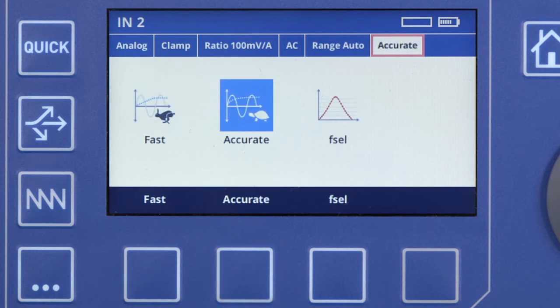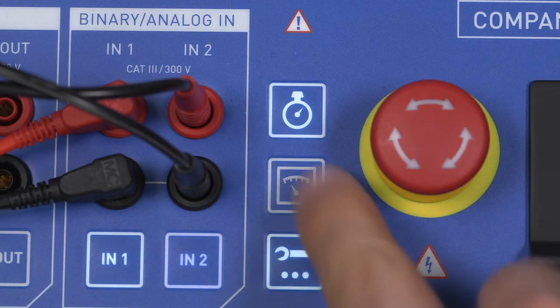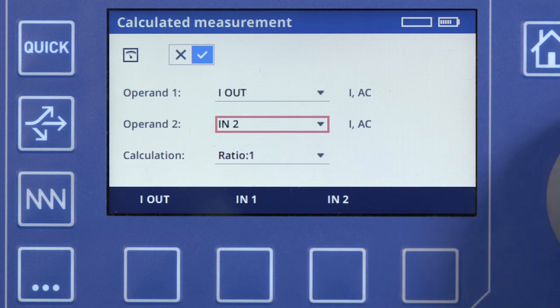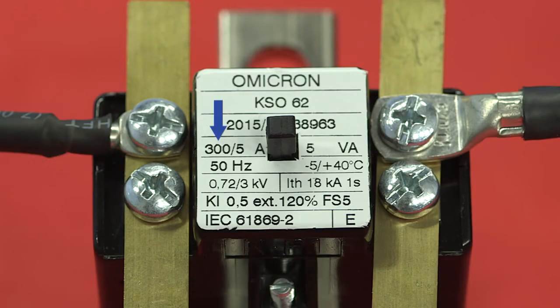Since a ratio cannot be measured directly, we need to define it as a calculated value based on our current measurements. We can do that by pressing the calculated measurement key, switching it on, and subsequently setting I out and IN2 to be our operands. Ratio to 5 will be our calculation setting. We are doing that since our demo CT has a 300 to 5 rating.